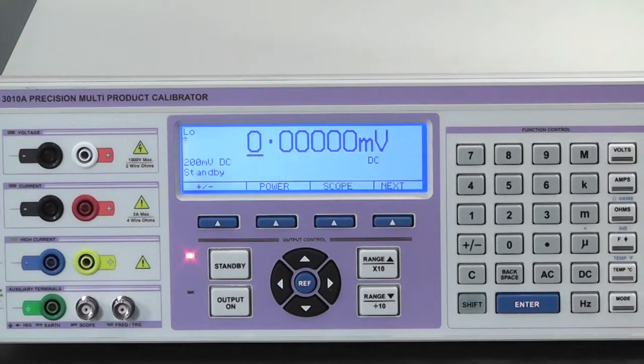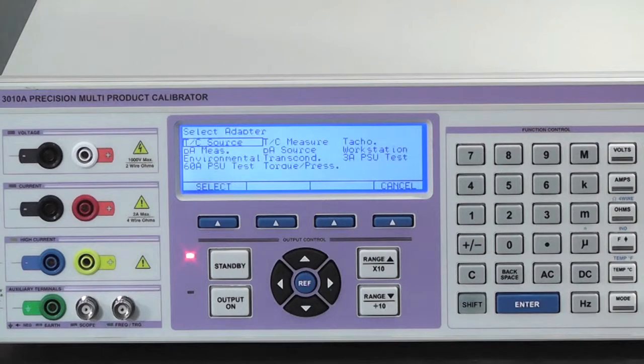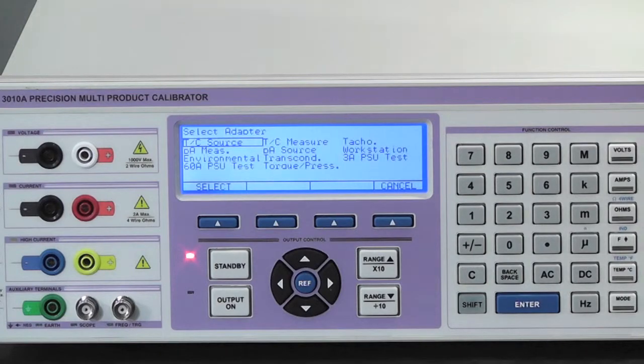To set up the calibrator use the mode key. This will then display the adapter menu. Then using the direction keys, either select TC source or TC measure.